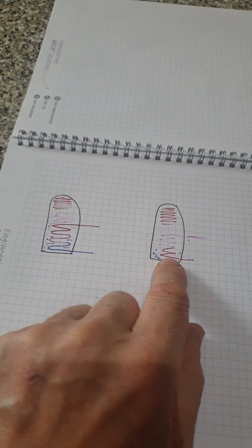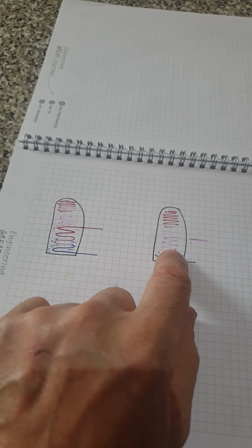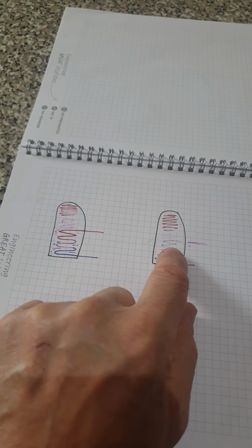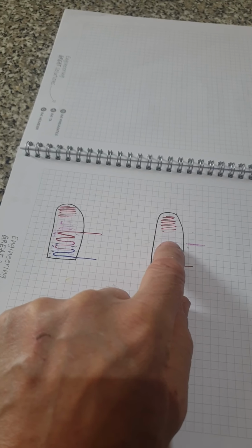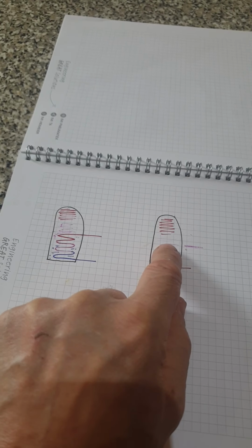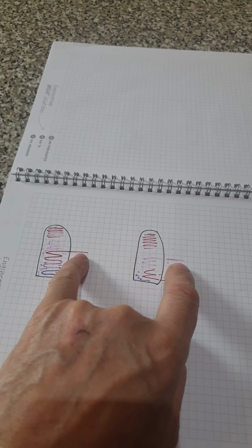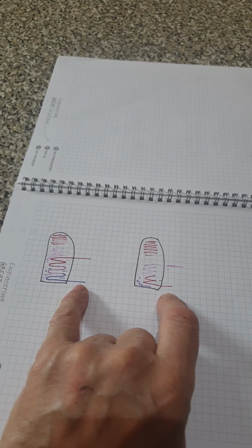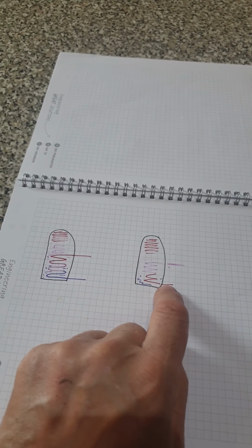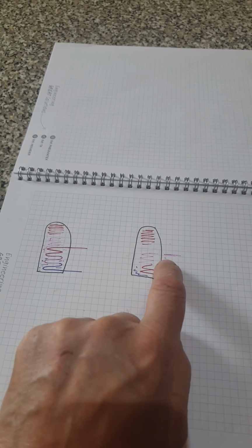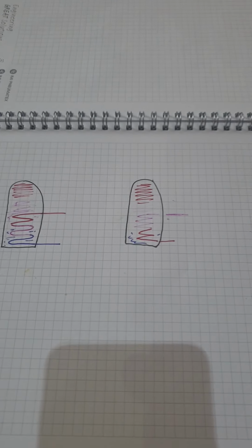If you're heating a cylinder from the bottom, then obviously as you get to the end, it reduces the amount of heat energy the coil can give up because it's then rising into the warmer water. So I've denoted that here as flow in hot, a return in blue, and here we've got the flow in red, and I've got an intermediate colour to represent a warm return.